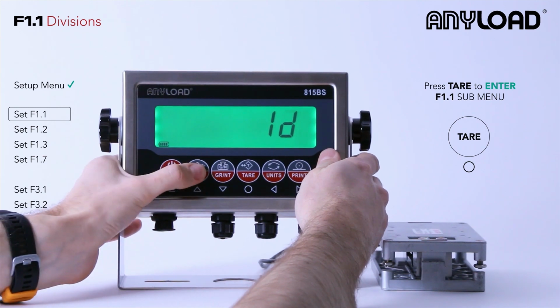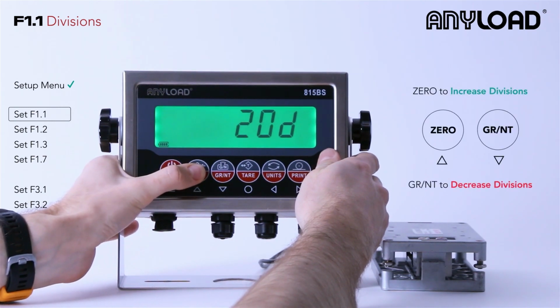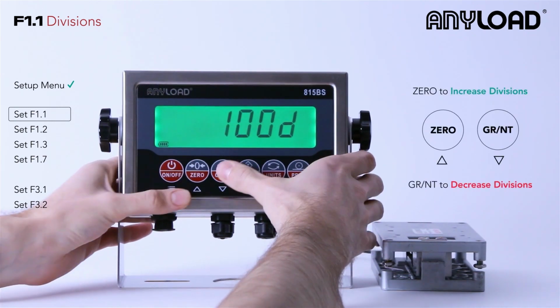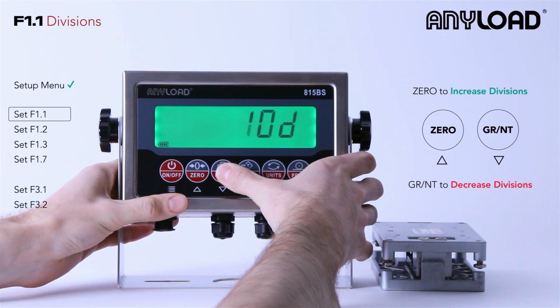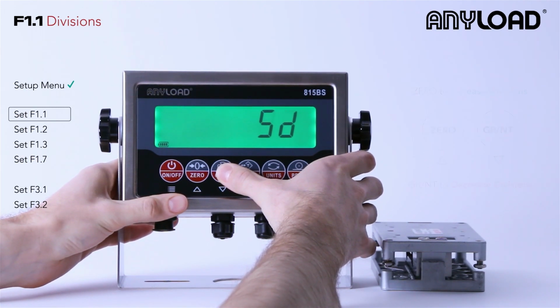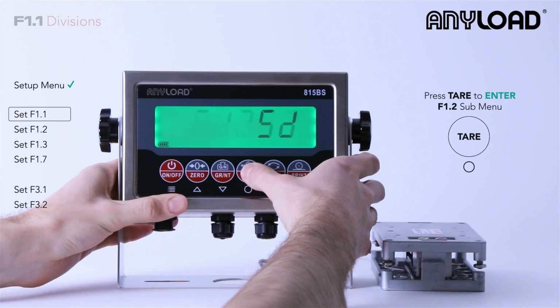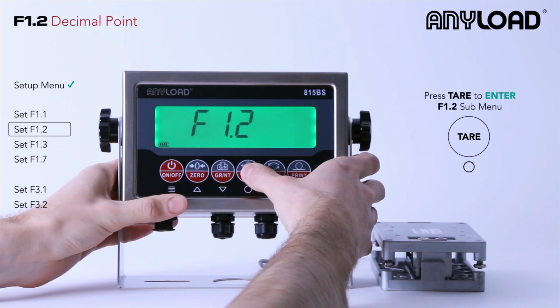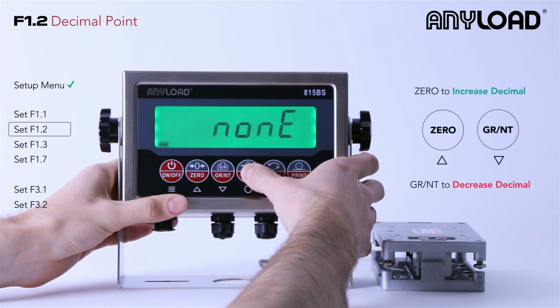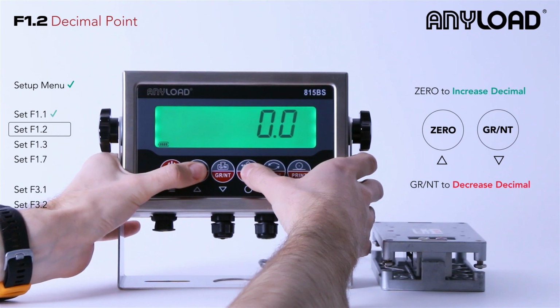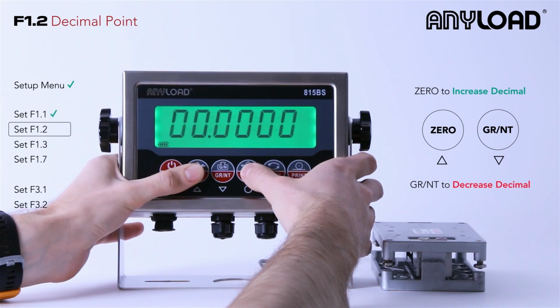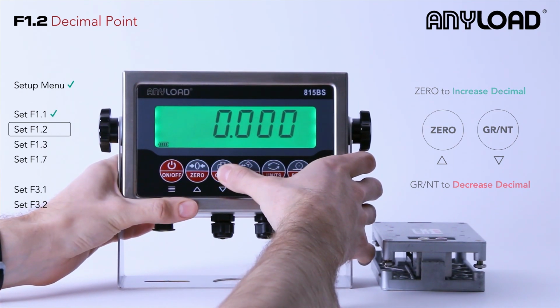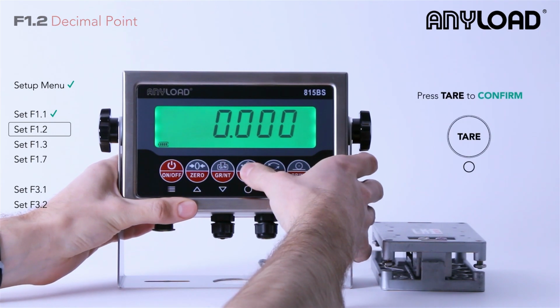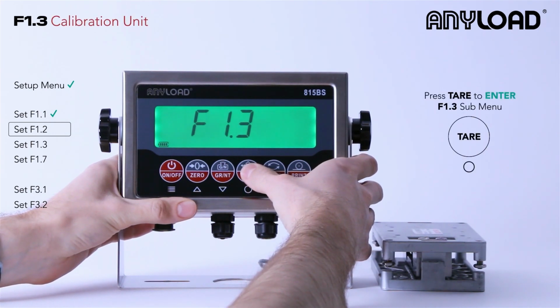So we wanted to set our divisions to 5. I can navigate up and down using 0 or the gross button, up and down respectively. So we'll navigate to 5 divisions, and I'll press tare to confirm that selection. F1.2 is going to be our decimal point. It's currently set to none. We wanted ours to be set to 3 decimal places, so I'll navigate up and down using those same buttons and press tare to confirm that selection.